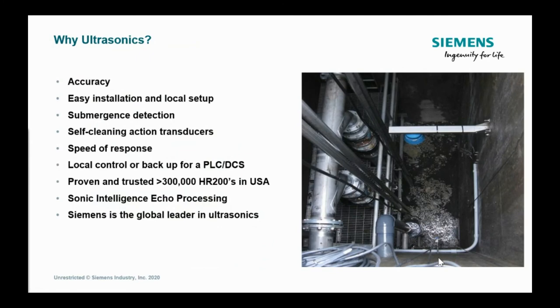Okay, they're pretty easy to set up. You can actually get some other data out of it, such as if the transducer goes submerged. Ultrasonic by nature is kind of self-cleaning, insofar as the face of it is active like a speaker. So sometimes you can literally flick off condensation or moisture off of the face of it. Ultrasonic tends to be a little bit faster in the measurement. The fastest technology is guided wave radar, but the speed of the application, how quickly it fills and empties, can be a factor. You can have local control or backup to a PLC, or the PLC can be local, or it can be the primary control, and you can have a backup local control with ultrasonics.